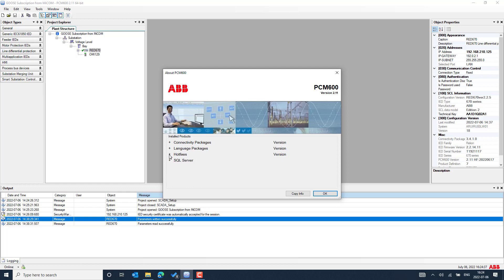As step two, if you are working with high voltage protection control IEDs, you need the dedicated connectivity package in the latest version. On top of that, you also need to install the IED modules for the specific IED type depending on the IED model you have. In the case of medium voltage protection, control, and automation IEDs, the connectivity package is specific to each model.